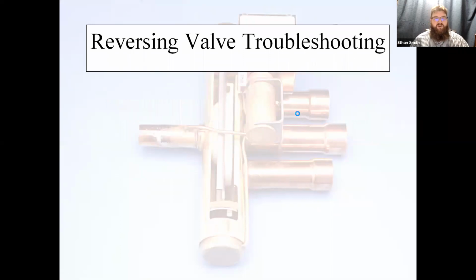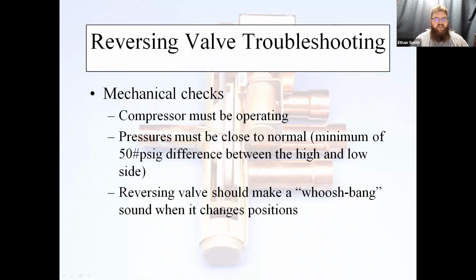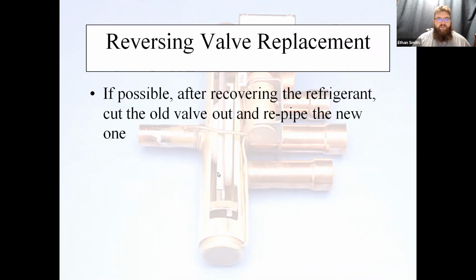But make sure that it's not any of these before you do that, because I have had guys go out, change reversing valves, and then run into the same problem because either they didn't check it electrically or they simply didn't have enough refrigerant in the system in order to make the thing move. Okay.